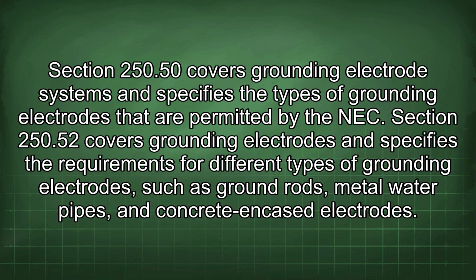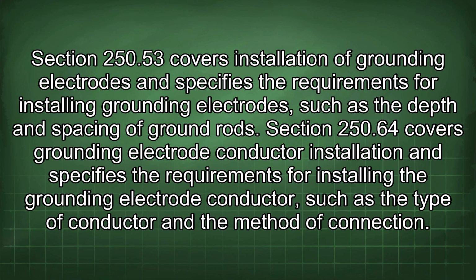Section 250.50 covers grounding electrode systems and specifies the types of grounding electrodes that are permitted by the NEC. Section 250.52 covers grounding electrodes and specifies the requirements for different types of grounding electrodes, such as ground rods, metal water pipes, and concrete encased electrodes. Section 250.53 covers installation of grounding electrodes and specifies the requirements for installing grounding electrodes, such as the depth and spacing of ground rods. Section 250.64 covers grounding electrode conductor installation and specifies the requirements for installing the grounding electrode conductor, such as the type of conductor and the method of connection.